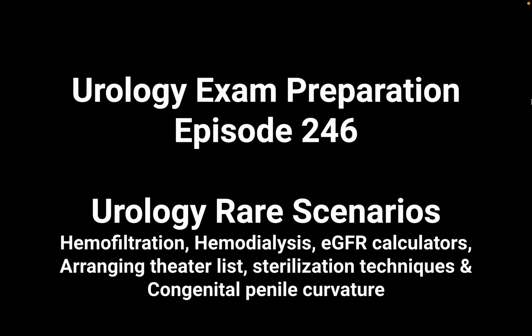Okay. Now, ETO sterilization is the one which works with the vacuum pack. ETO stands for a type of gas sterilization, ethylene oxide. It is very useful for instruments which are very fragile and susceptible to breakage, especially in high temperature or high pressure. After the ETO gas-based sterilization, the whole instrument will be packed and covered by two layers of plastic in the front and back, like a blister pack which you open and then use the equipment. That is one of the easiest and best methods for sterilizing the flexible cystoscopes used in the ward. Okay? Thank you. Good.